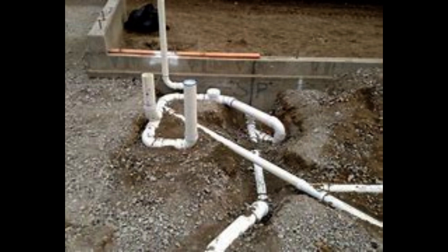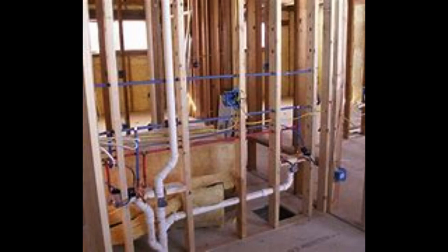The absence of an opening that would allow access to equipment for inspection, service, repair, or replacement without removing permanent construction or building finish. 10. When applicable, a floored passageway and service platform that would allow access for equipment inspection, service, repair, or replacement.